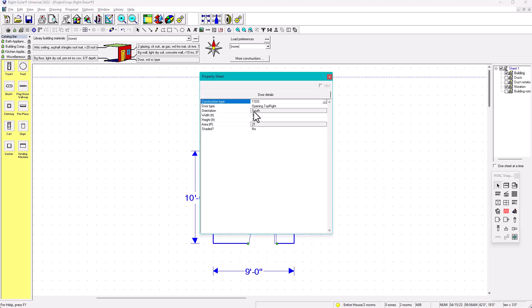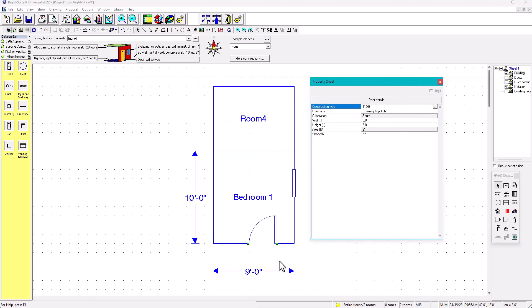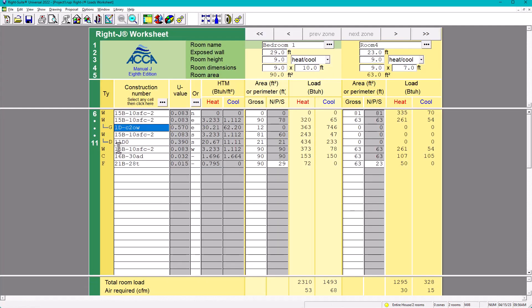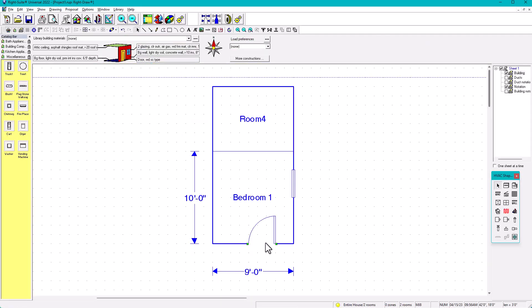For example, if we put a 3 by 7 door on the exposed south wall, that door is exposed. It has 21 square feet of area. In the property sheet, the south wall has a gross area of 81. Subtract the door: 81 minus 21 equals 60 square feet of net free wall area. This matters because it's an exposed element in heat load calculations.